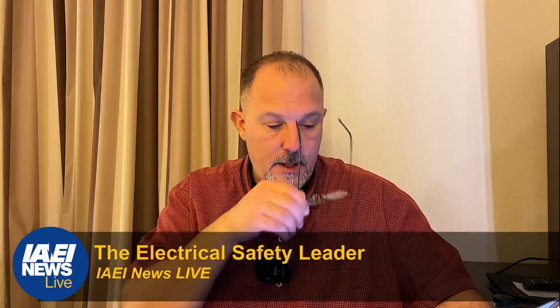So that is very generic. That means that it's any type of contact device. It doesn't have to be what you're probably picturing in your mind with regard to a receptacle. It could be any contact device. Then it says a single receptacle. Oh boy, this is important. And sometimes people just don't get it. So, a single receptacle is a single contact device with no other contact device on the same yoke or strap.